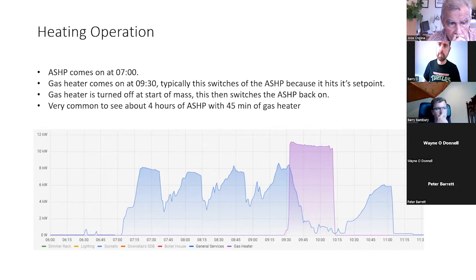What we also see happening is as soon as that gas heater comes on, it's blowing really warm air in at about the same height as where the cassettes for the air source heat pump are. So the temperature probe on the output, or this is what we assume is happening because it happens every time, as soon as the gas heater comes on, the temperature probe on the output of the air source heat pump goes, oh yeah, I've reached my set point, I turn off. So you don't ever have the two of them working together.